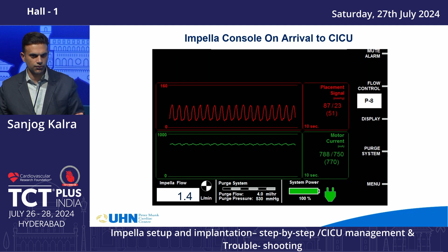The pump flow tells you how much you're venting per minute, in liters per minute. This is not the algebraic sum, this flow plus the right heart cath, to determine your total cardiac output. It's not an algebraic sum because ultimately the pump and the heart are both pumping the same blood. And your P level, your flow control, tells you approximately where on the Impella scale of flow you are, where higher P rates mean the device is functioning with higher flows and lower P rates mean lower flows. So that in a nutshell is what you're looking at on an AIC.